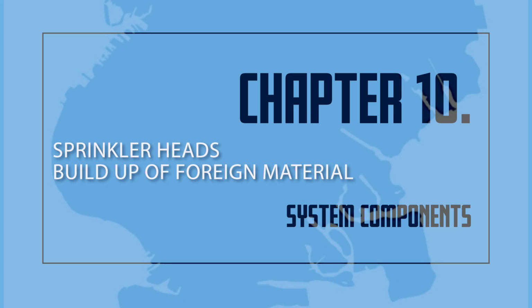Deposits of light dust are less serious than hard deposits. Dust buildup may delay the operation of sprinkler heads. However, it will not prevent the eventual discharge of water. Dust deposits can be blown or brushed off. If a brush is used, it should be soft to avoid possible injury to sprinkler parts.